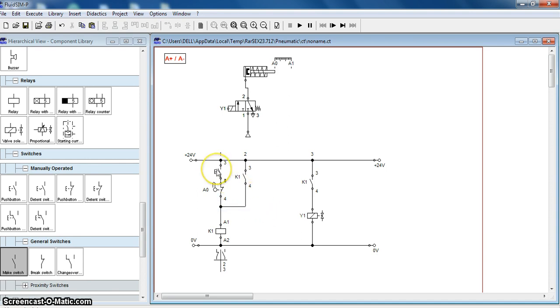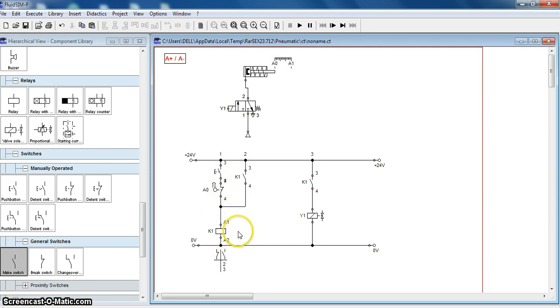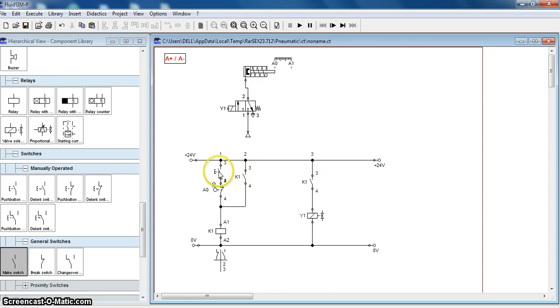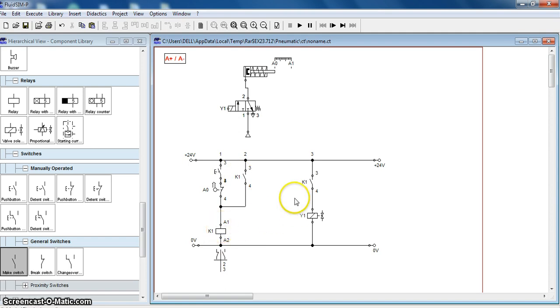When we press the push button, A0 is initially activated because the cylinder is retracted. Current flows and K1 gets energized. When K1 gets energized, its contacts — which are normally open — get closed. So even if the push button is released, there is a flow of current and K1 relay remains energized. When K1 gets energized, Y1 is energized.